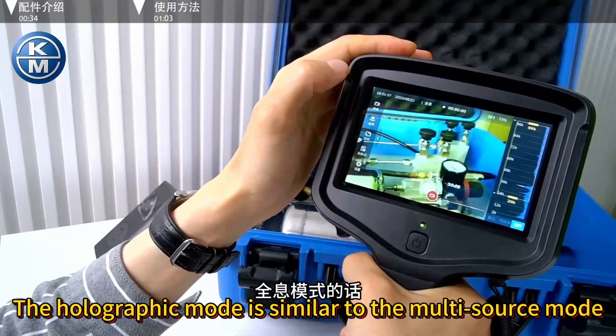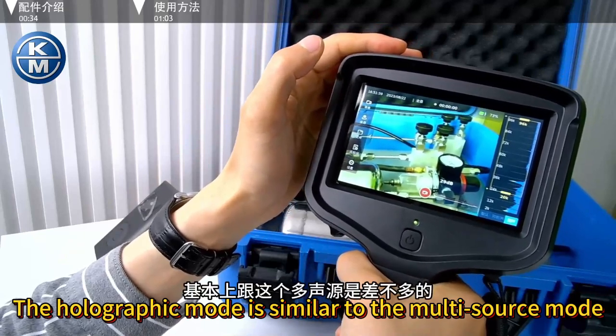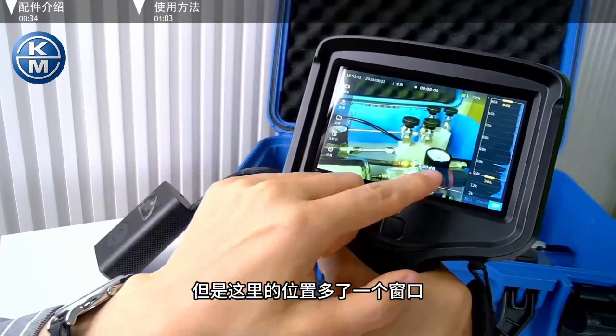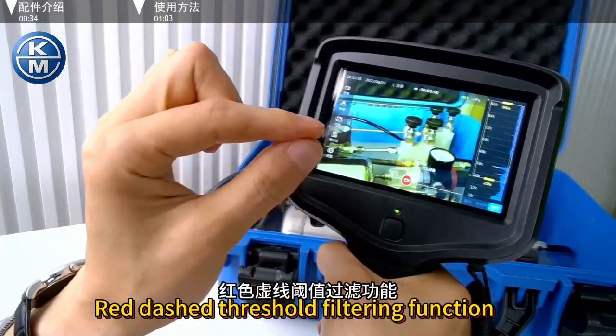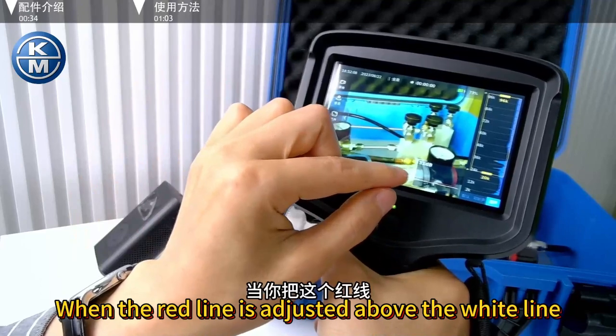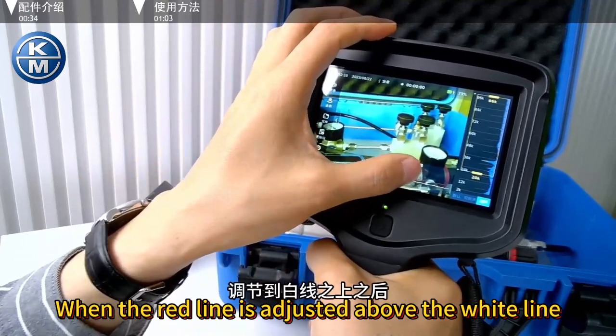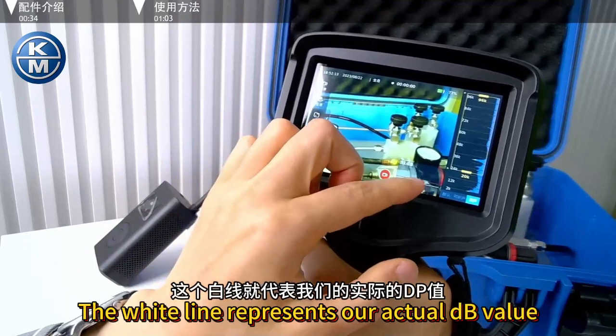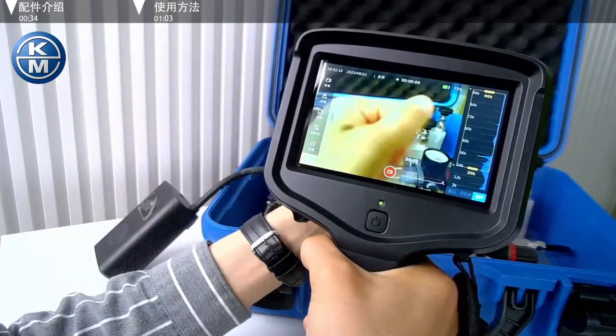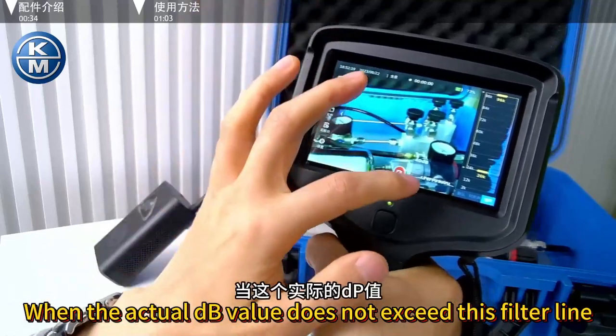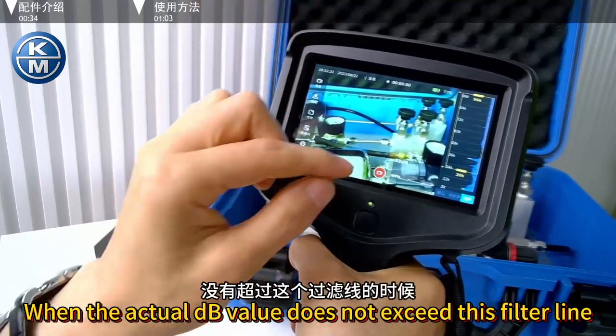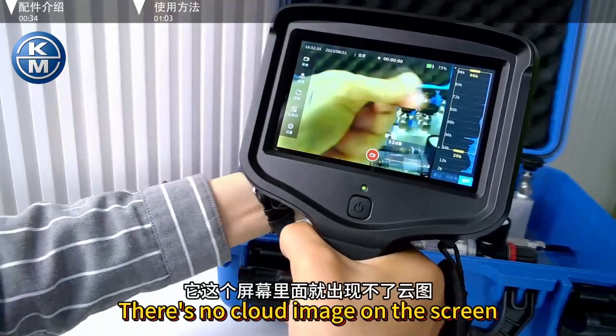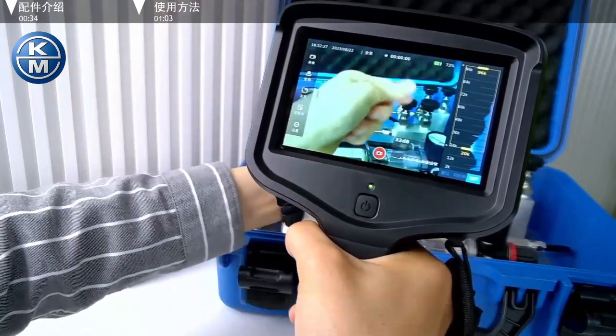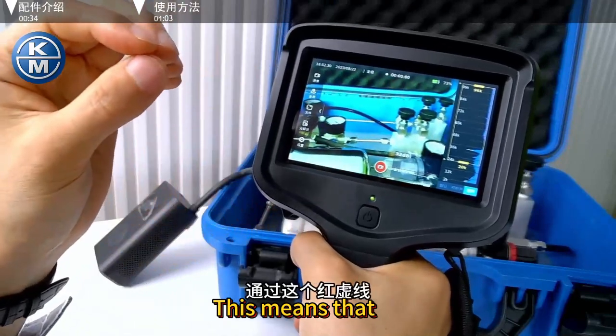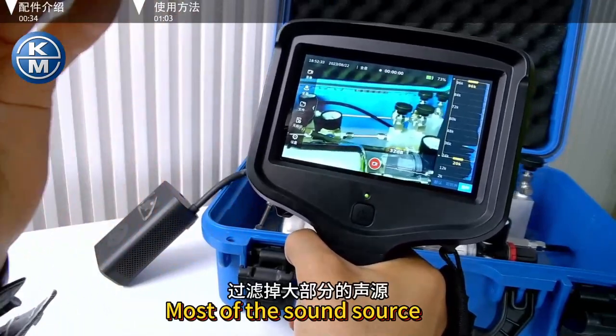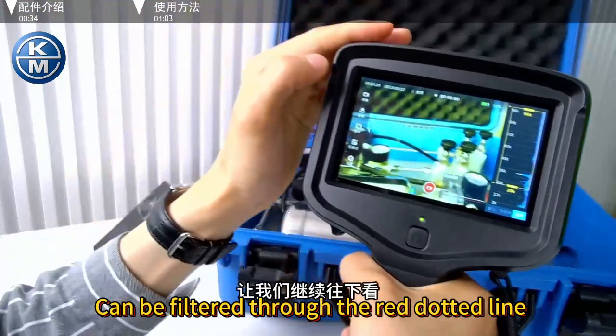The holographic mode is similar to the multi-source mode, but there's an extra window on the bottom right. Red dash threshold filtering function. When the red line is adjusted above the white line, the white line represents our actual dB value. When the actual dB value does not exceed this filter line, there's no cloud image on the screen. This means that most of the sound source can be filtered through the red dotted line.